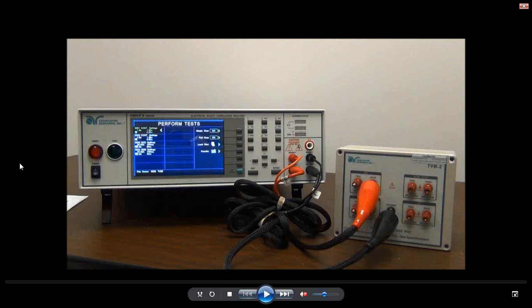The first test that we're going to run here is to verify the ground continuity, and the next one, within this video, would be how we can use the TVB toolbox to verify the ground bond test. If you can see in the picture, the two red cables, sense and current, are terminated into an alligator clip that's connected to the pass side of the ground continuity, and the black return and sense cables, also terminated into an alligator clip on the other end, are connected to the return side of the TVB toolbox, as we discussed earlier.